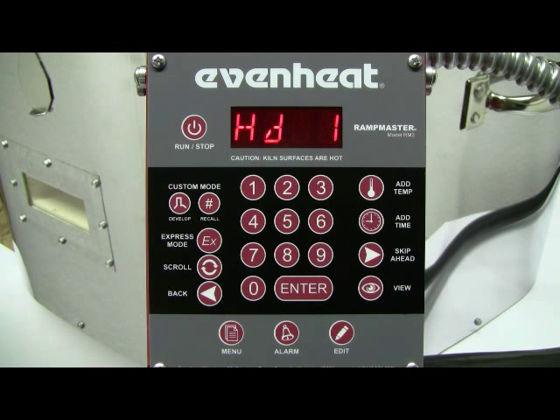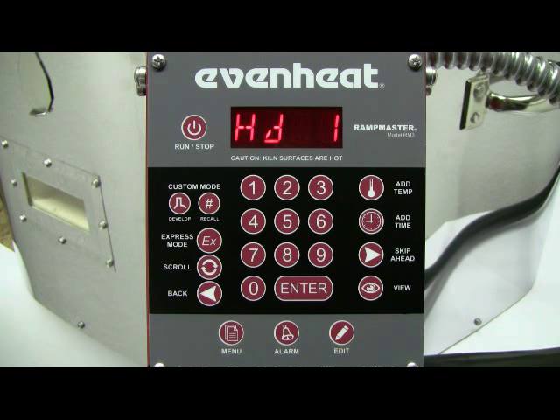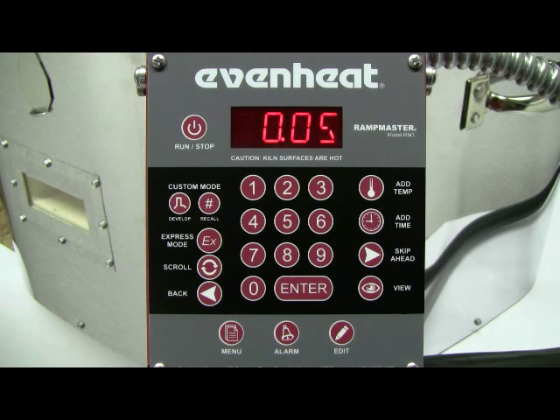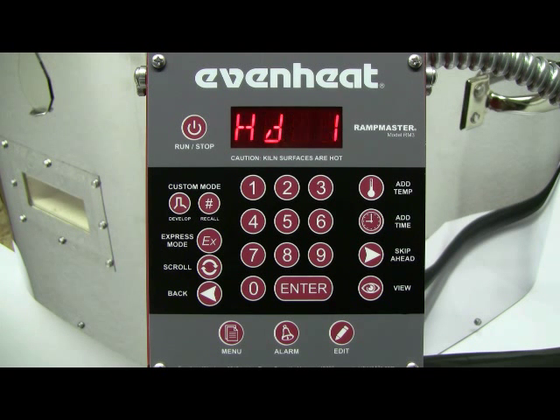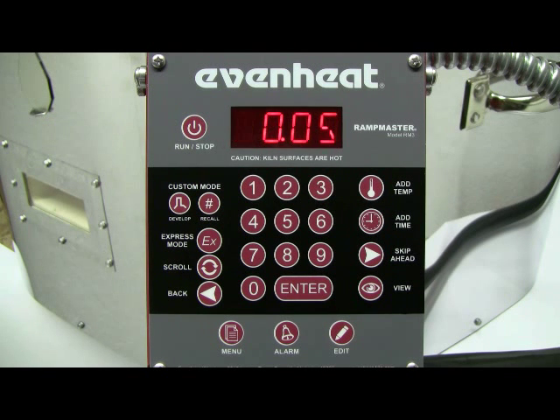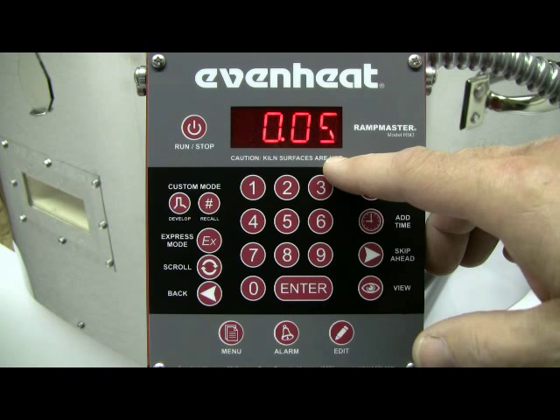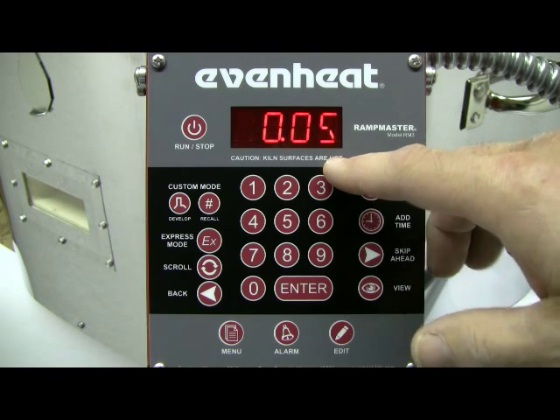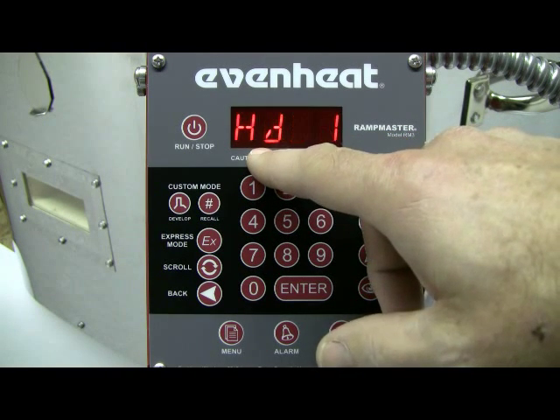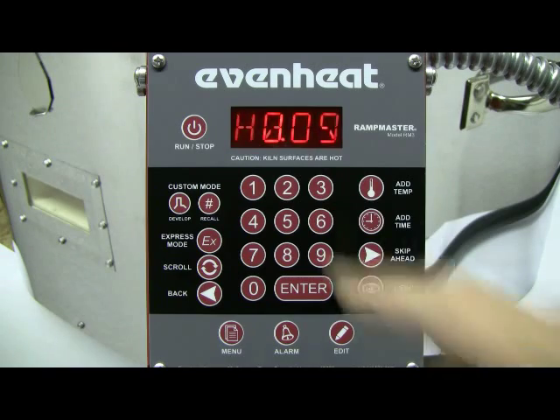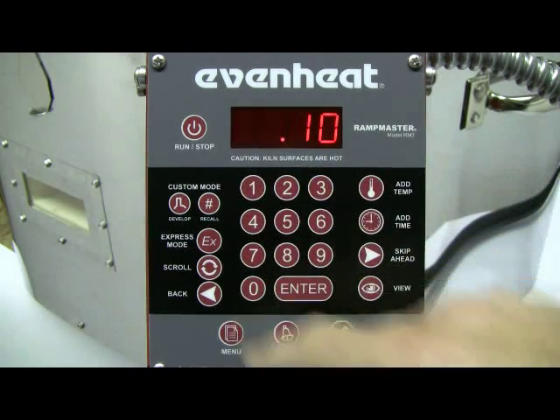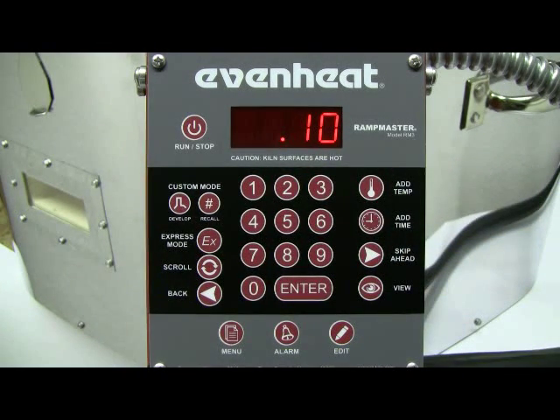The display now reads HLD1. The RampMaster is asking for the desired hold time at our segment 1 temperature. For this example, we'll hold at our 1000 degrees for 10 minutes. Hold time is programmed in hours and minutes — values to the right of the decimal point are in minutes and values to the left are in hours. Type in 10, then press the ENTER key to store your choice.